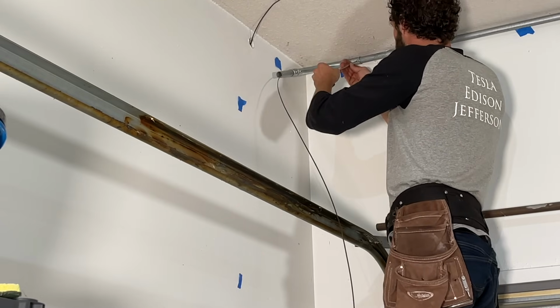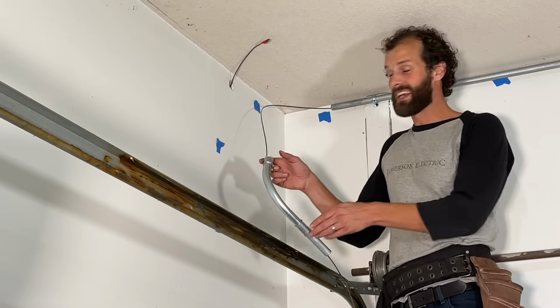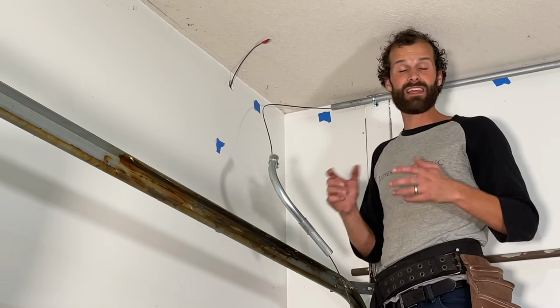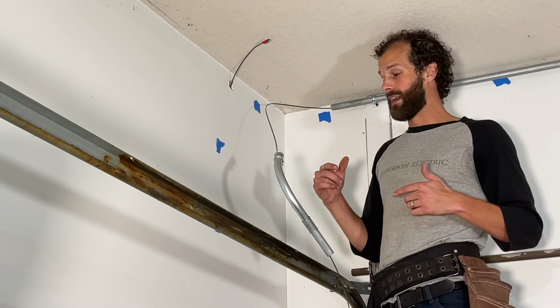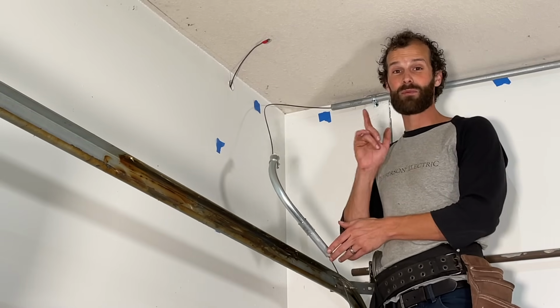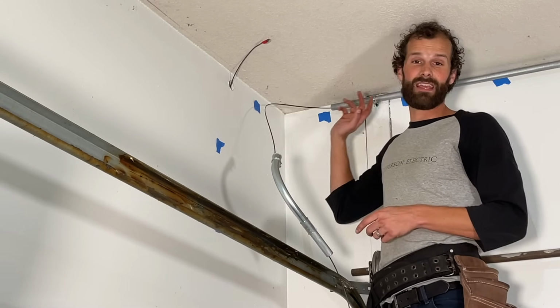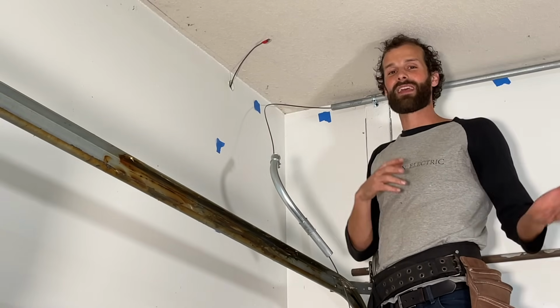Remove this fitting. At this point, there's enough friction in the pull, every coupling, every connector, every 90, even the length of pipe, that you electricians out there are going to call me on it, because conduit systems are supposed to be complete before the insertion of wire. But we're going to ease our resistance. We're going to get the pull complete.